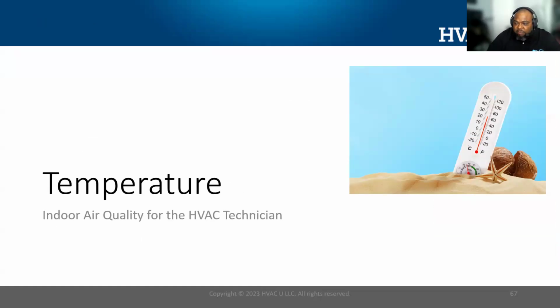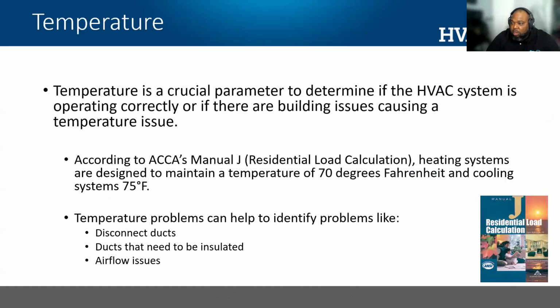And temperature is our final IAQ parameter. When we talk about temperature, temperature is critical to determine if a system is operating correctly. Now, many people may say, "Okay, temperature, I don't necessarily see that one as being an IAQ concern," and we get that comment or statement a lot, but it's actually really critical to identify it as an IAQ concern. Well, measuring temperature will help us identify other problems, such as disconnected ducts, ducts that may need to be insulated, or airflow issues, which can contribute or compound other IEQ problems.